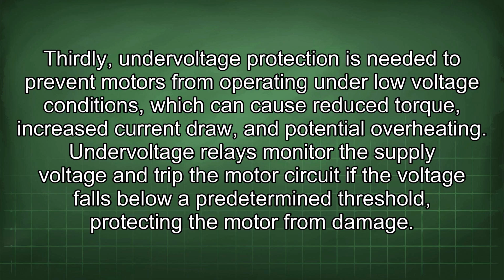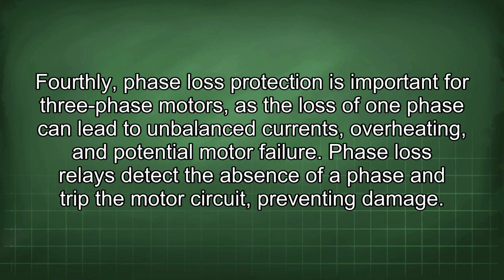Thirdly, undervoltage protection is needed to prevent motors from operating under low voltage conditions, which can cause reduced torque, increased current draw, and potential overheating. Undervoltage relays monitor the supply voltage and trip the motor circuit if the voltage falls below a predetermined threshold, protecting the motor from damage. Fourthly, phase loss protection is important for three-phase motors, as the loss of one phase can lead to unbalanced currents, overheating, and potential motor failure. Phase loss relays detect the absence of a phase and trip the motor circuit, preventing damage.